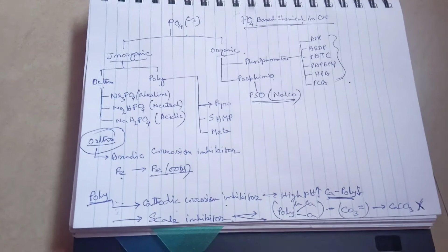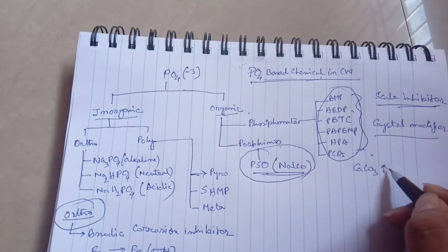Now comes the organic phosphate. All of the organic phosphates act as scale inhibitors. How do they act as scale inhibitors? Each of them acts as a crystal modifier. What is a crystal modifier? Once a calcium carbonate crystal has been formed, the presence of any of these organic phosphates basically alters or destroys the crystal structure. Once the crystal structure of calcium carbonate is destroyed, it cannot attach with other calcium carbonate crystals and form crystal growth. So these phosphates act as crystal modifiers. They distort the calcium carbonate crystal so that one crystal cannot be attracted by the other one and it cannot build up the crystal layer. That's how it prevents scale.